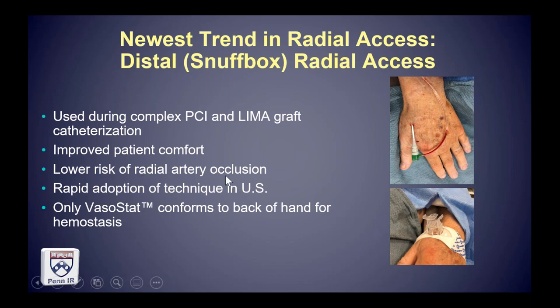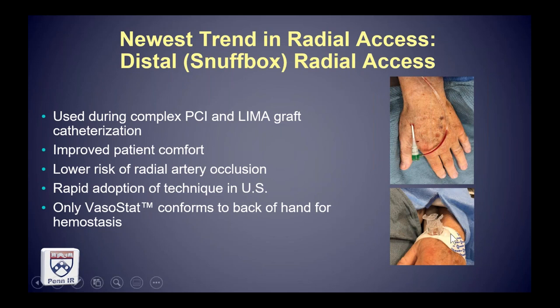It was also found to have a lower risk of radial artery occlusion and was rapidly adopted initially in Japan, India, and then throughout the rest of the world including the US. This was actually serendipitous during device development because all the other balloon-type devices failed miserably for dorsal radial access unless dismantled or taped up with cumbersome tape. The VasoStat device conforms perfectly to the back of the hand for hemostasis of the dorsal or distal radial artery.